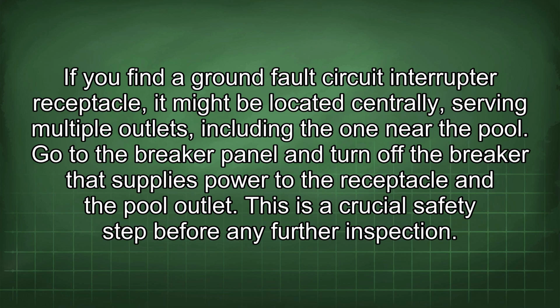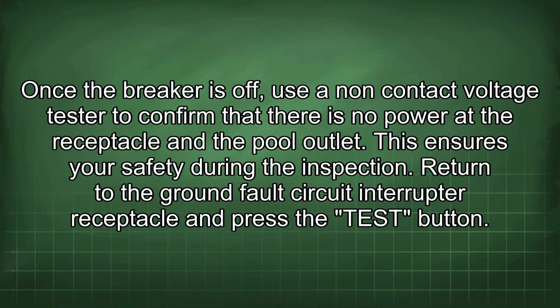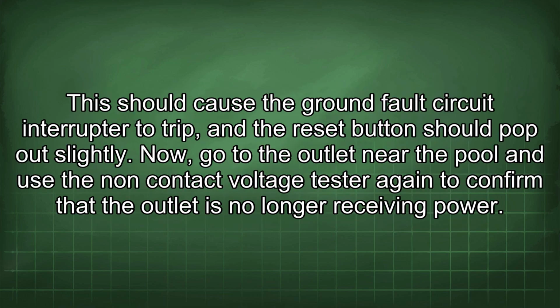Go to the breaker panel and turn off the breaker that supplies power to the receptacle and the pool outlet. This is a crucial safety step before any further inspection. Once the breaker is off, use a non-contact voltage tester to confirm that there is no power at the receptacle and the pool outlet. This ensures your safety during the inspection. Return to the ground fault circuit interrupter receptacle and press the test button. This should cause the ground fault circuit interrupter to trip, and the reset button should pop out slightly.